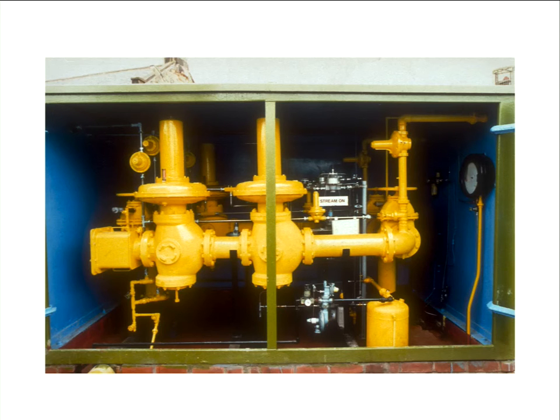So this is a 2-bar system. This is my normally controlling one, so I'll set that at 2-bar via the spring setting, or the spring in a pilot here, and it stays fixed. It sits at 2-bar, and it's just trying to hold 2-bar in that system. And the planners have looked and said 2-bar is enough to meet all the possible demand that can occur in that downstream system, even on the coldest.